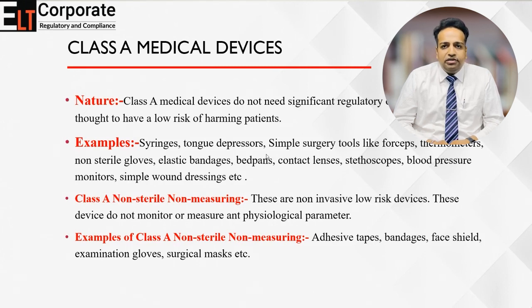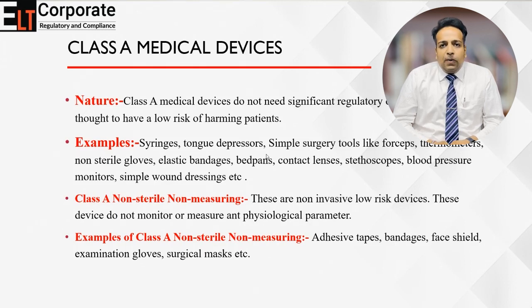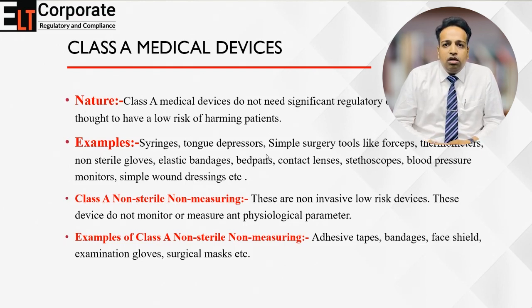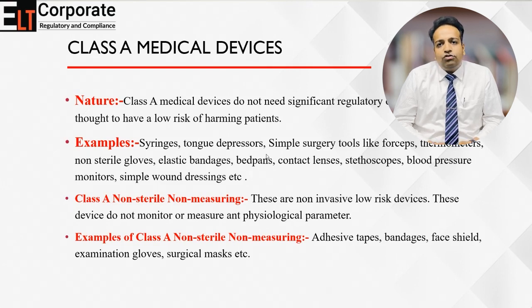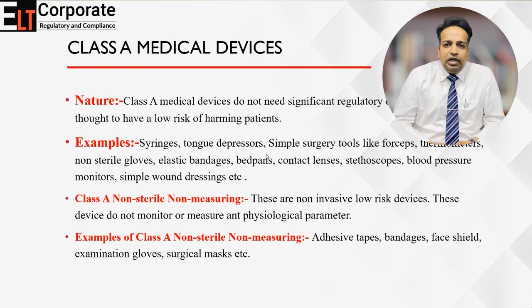The government has recently further classified Class A instruments into non-sterile and non-measuring devices. Basically, any equipment which doesn't require sterilization before it is released into the market, and which is also not a measuring device — in such cases the government has given the option of simplified registration over the CDSCO portal. That is why the government has further classified Class A devices into non-sterile and non-measuring devices.